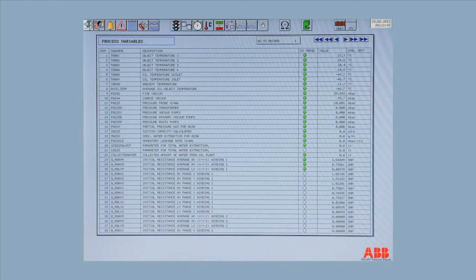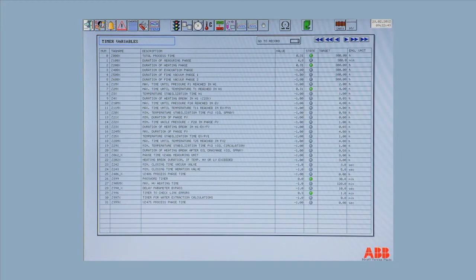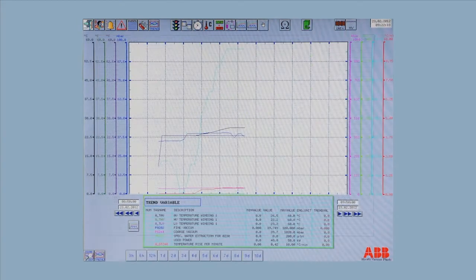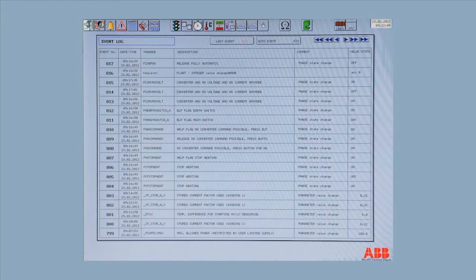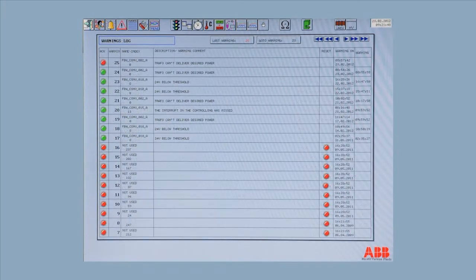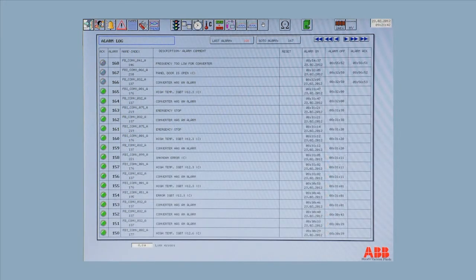One can choose which process variables to trend. Click on the virtual button to make it green to turn on. You can also see the respective values for each of the parameters. There are a series of screens which group process variables, such as the timer variables and the trend variables screen, that plot the values of variables of interest as a function of time. Of course, there are event logs, warning logs, and alarm logs. The operator needs to know the significance of each of these and what action needs to be taken and when.